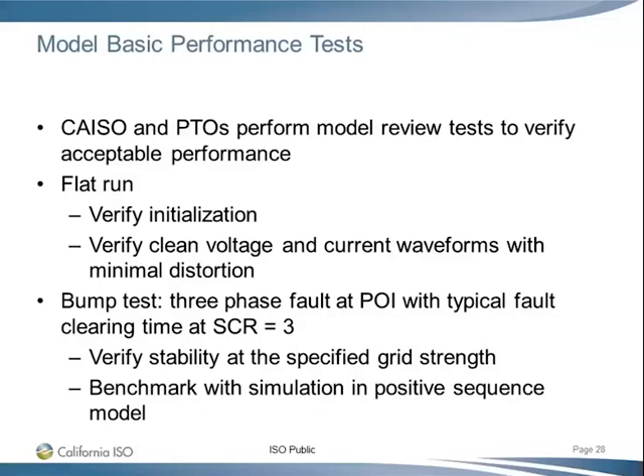So it's 230 kV or 500 kV, and the fault is 4 cycles. So we'll test that at a short circuit ratio of 3. And we do require your model could work at this 3, but typically EMT models can work at SCR much lower than this. It's based on the condition we have in our system. We feel like we'll test the model at SCR 3. That's reasonable, at least for now.